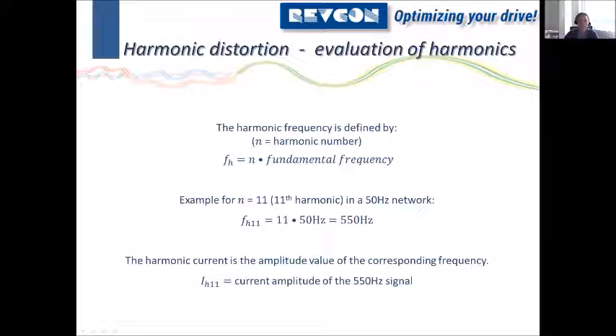Not a topic of today, just to mention there are interharmonics and there are harmonics. Harmonics are whole numbers, integer multiples of the fundamental frequency. Simple example, the 11th harmonic is 11 times the fundamental frequency. So with 50 hertz, it will be 550 hertz. If it's the 10th harmonic, then it's 500 hertz and so on. I think the principle is quite simple. Okay.